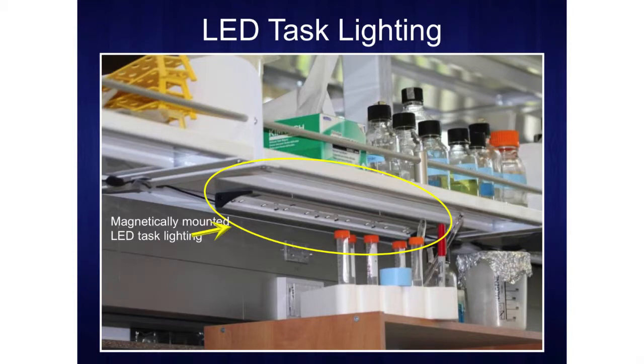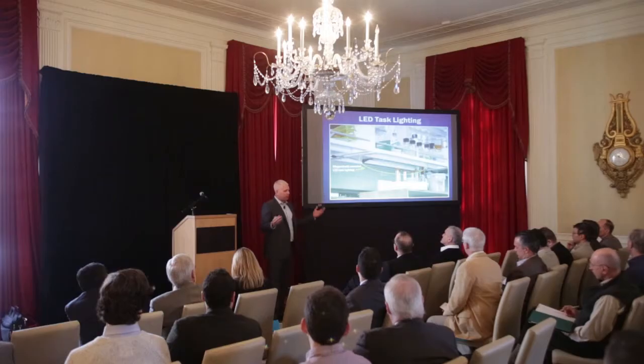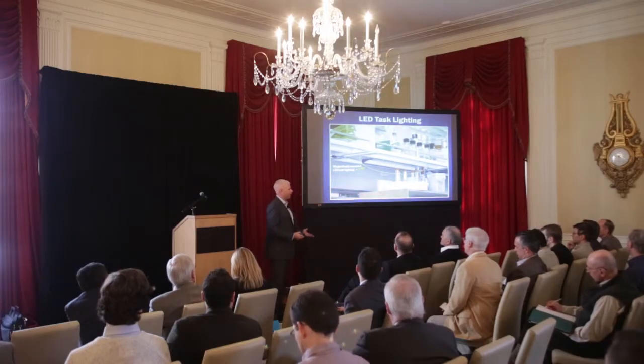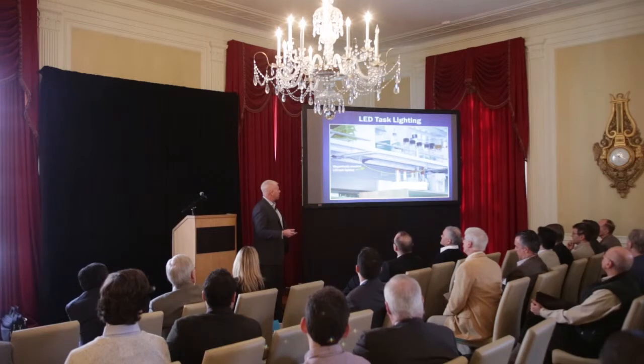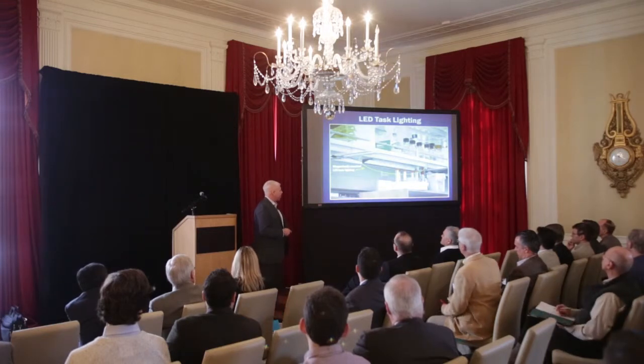And then magnetically mounted task lighting. If we've lowered our lighting power density and we want users to be conscious of how much energy they're using, and they still have to do fine pipetting or whatever work on the benchtop, we provide them with magnetically mounted task lighting. Put it where you need it, but don't put it everywhere. If I have a large piece of equipment, like a shake table, I don't need that magnetically mounted task lighting there. So we give them the option to put it where they need it.